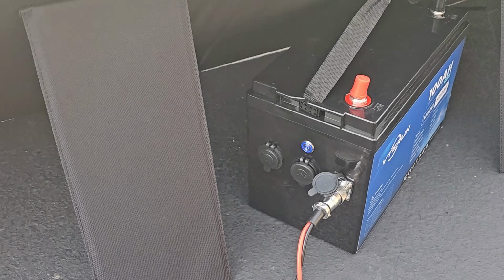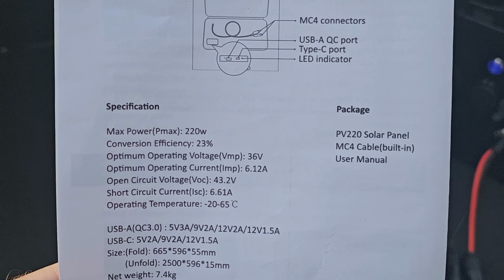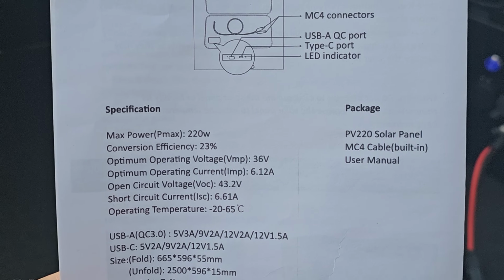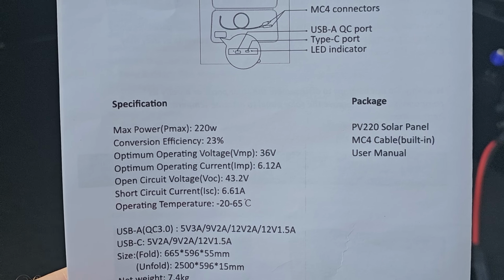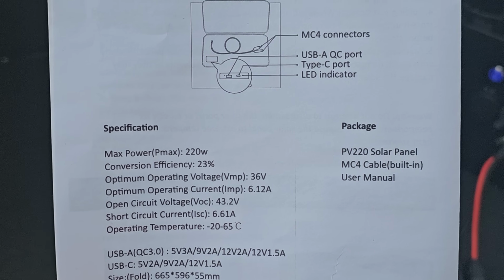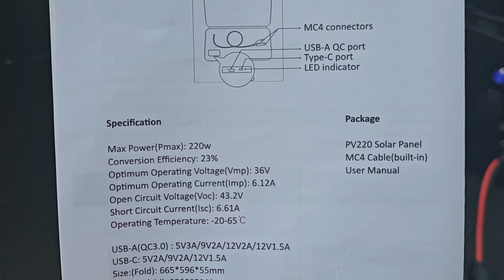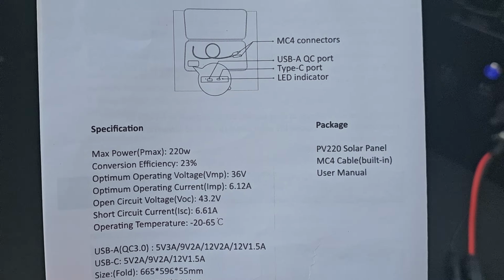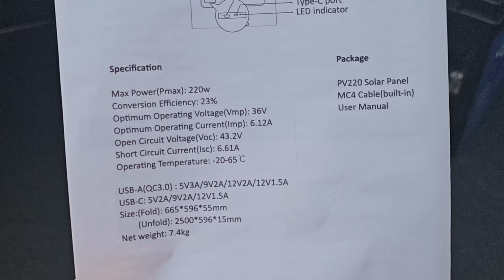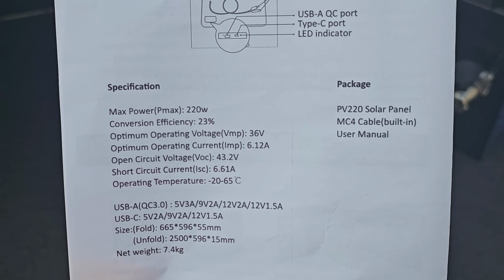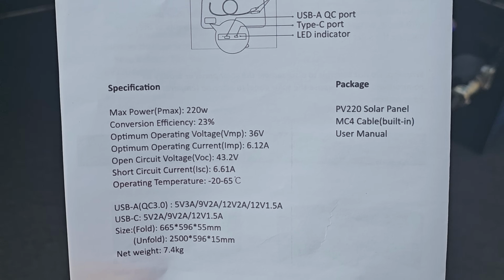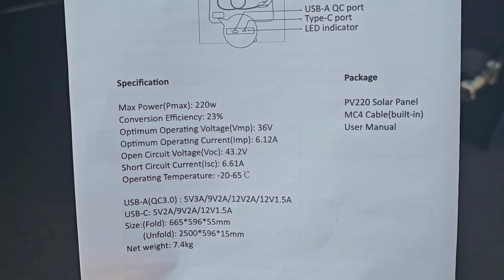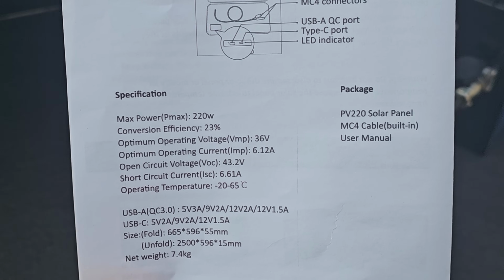Now I will say the solar panel specs are kind of interesting. This is not a solar panel you'd want to put in series with another one of these on very many power stations, because it has a voltage open circuit of 43.2 volts. If you recall, the voltage input spec on this battery has a max of about 45 volts. So this panel is especially well suited for this particular battery with that MPPT charge controller in it, because of that high voltage open circuit.